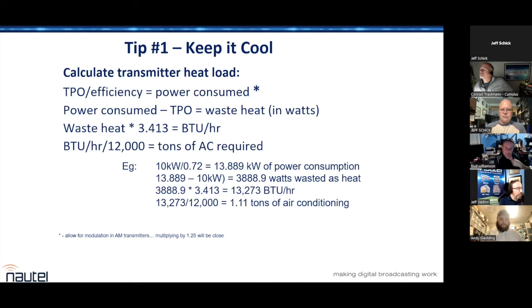Now, if you put that equipment in the building and the sun shines down, the building's going to heat up, so you've still got convection heat to factor in. I've had people who got this heat load number from me, very dutifully installed a transmitter, sized the air conditioner to that number, and then wondered why it didn't do the job in the summertime. So that's definitely one of those other things you want to factor in.